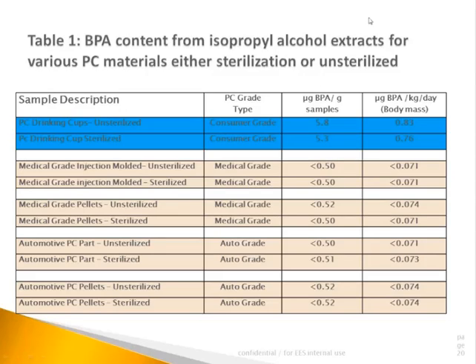The IPA extraction results indicated, with the exception of the drinking cups, which is the consumer-grade polycarbonate, BPA concentrations were well below the level of detection. This was evident from the rest of the data. In fact, the amount was less than 0.5 microgram per gram sample. BPA found in the drinking cups was 5.8 microgram BPA per gram for the unsterilized condition versus 5.3 microgram BPA per gram sample for the sterilized equivalent. Next slide.